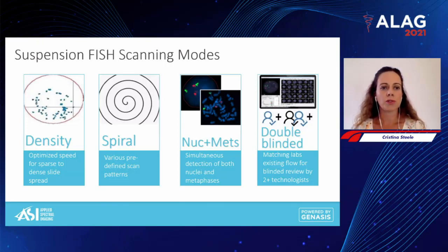So the microscope will start off at a 10x objective and scan the whole probe region first and identify the areas with the highest cellularity, so that it will return to those areas first with a high power objective to perform image capture. The scanner is set up to have stop criteria that are built in. So for example, it will stop after it has captured 400 cells, if that's your cutoff value, or 20 minutes.